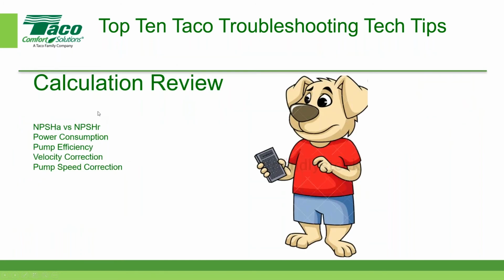I'm going to start doing some calculations, and I'm going to do a calculation on the net positive suction head available versus the net positive suction head that's required. We just said from looking at the pump curve data that the required NPSH is around 9 feet. I also figured out what the power consumption was by taking the readings of the voltage and the amperage. And remember what I said in the first example, let's assume that it did not have a variable frequency drive. If it did have a variable frequency drive, then we'd want to measure the voltage and the amperage at the input of the drive.